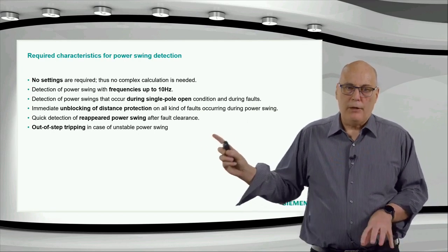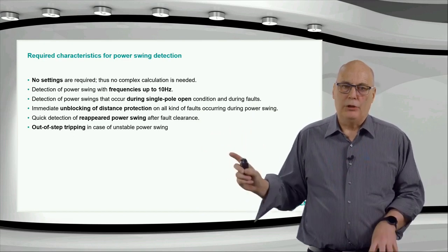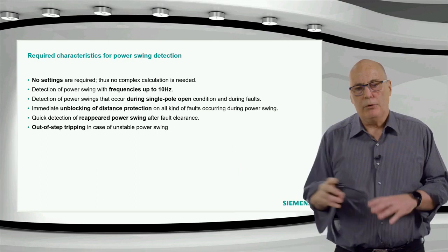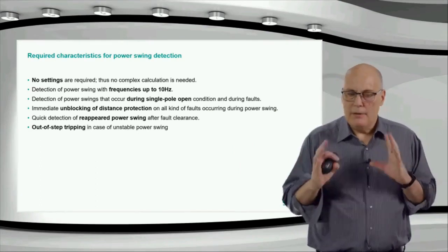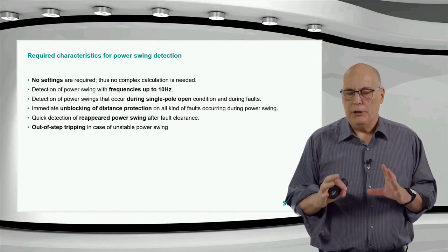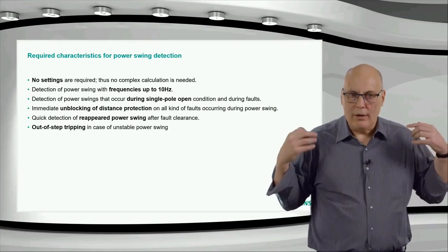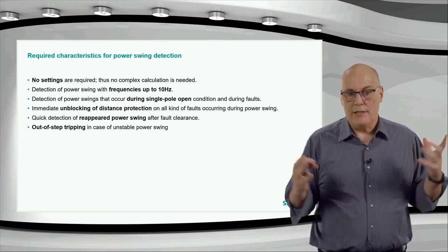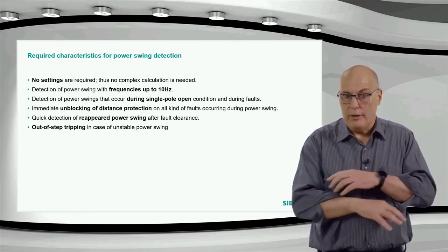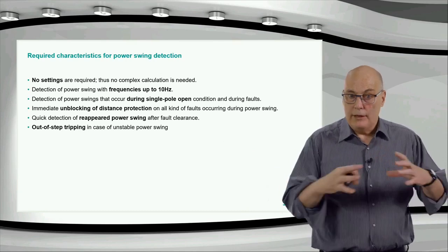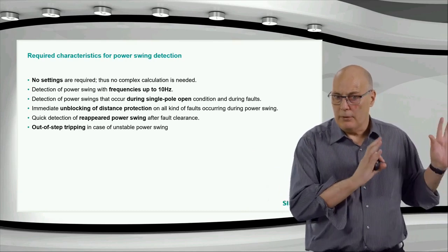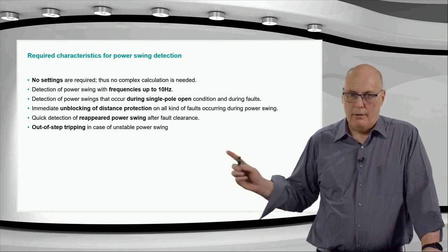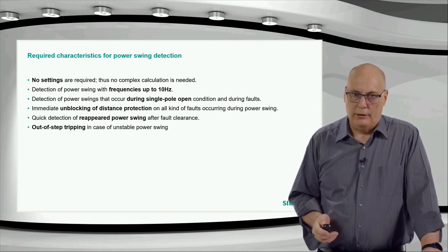Out-of-step protection in SIPROTEC 5 is a separate function, okay, that you would use. If you want to use out-of-step protection, it's the same principle behind it, but it's a different thing. It's not distance protection. It's a function that you apply to recover from, say, a disaster, one can call it. If the system has a real serious disaster, like cascading tripping, then you need to island the system. It's a separate concept, not a distance protection concept, and therefore it's a separate function, out-of-step protection function in the SIPROTEC 5 relays.